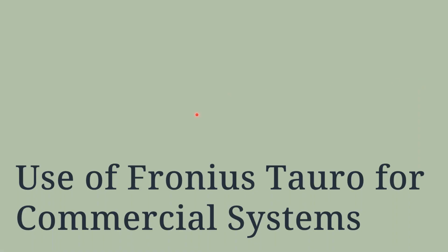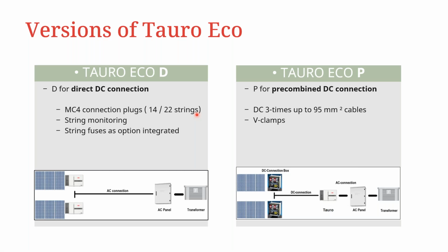So let's now go through the Fronius Tauro inverters and their use in commercial systems. With the Fronius Tauro, we have two variations. We have the Fronius Tauro Eco D version, or the direct version, and the Fronius Tauro Eco pre-combined version. With the D version, this basically means that you can connect your string power directly to the inverter, and this is done by way of MC4 plugs that are provided on the DC connection area of the inverter. If you have the 50 kilowatt version, you can connect up to 14 strings, and with the 100 kilowatt version, you can connect a maximum of 22 strings. This makes it possible to do string monitoring, and then the string fuses can be integrated as an option within the inverter.